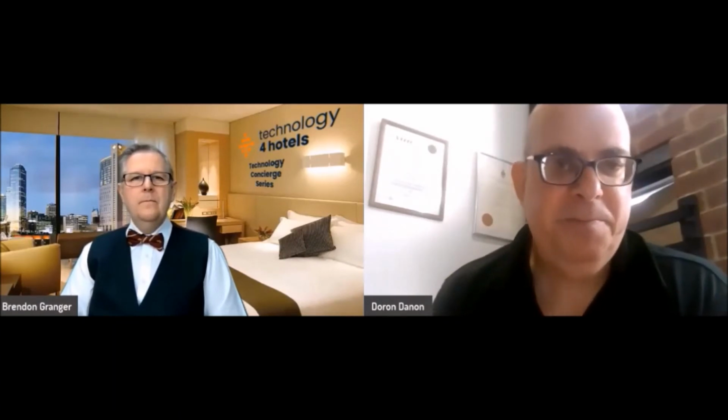So when the guest was out, rooms were kept at around 23, 24 degrees. Just that 2 degree difference in cooling, because they were in an extreme climate and paying a very high cost of power, got their money back in 6 months. That's sort of an ideal situation, but not all hotels are in the luxury position of having such high cost of power and such extreme climate conditions.